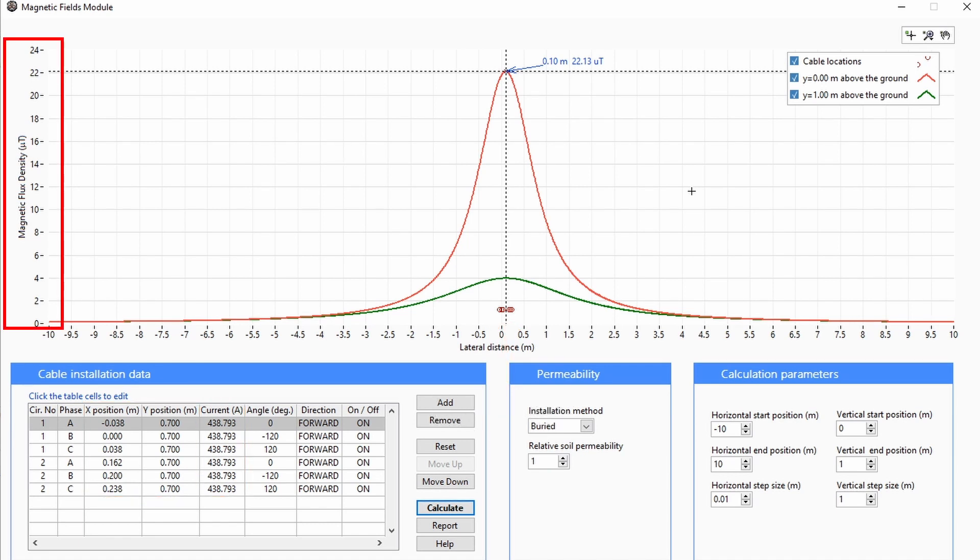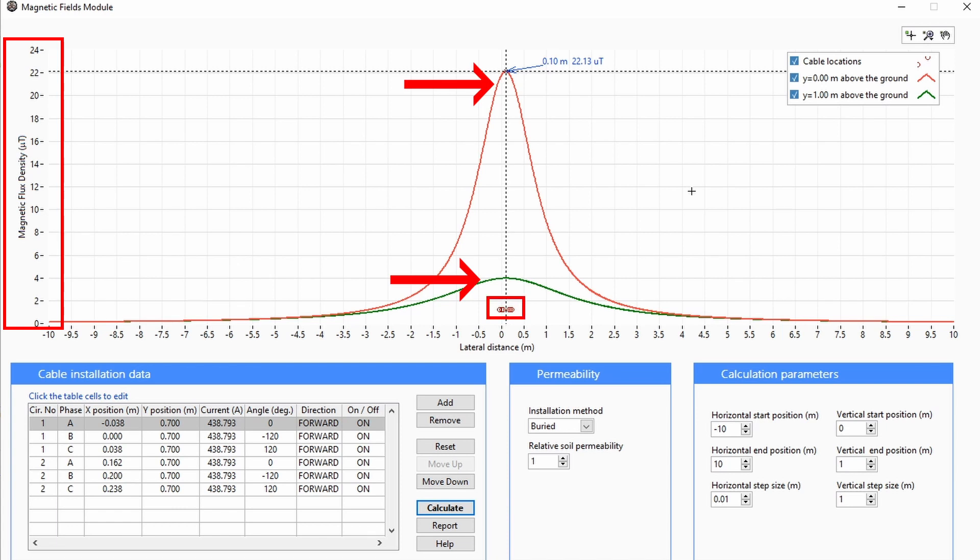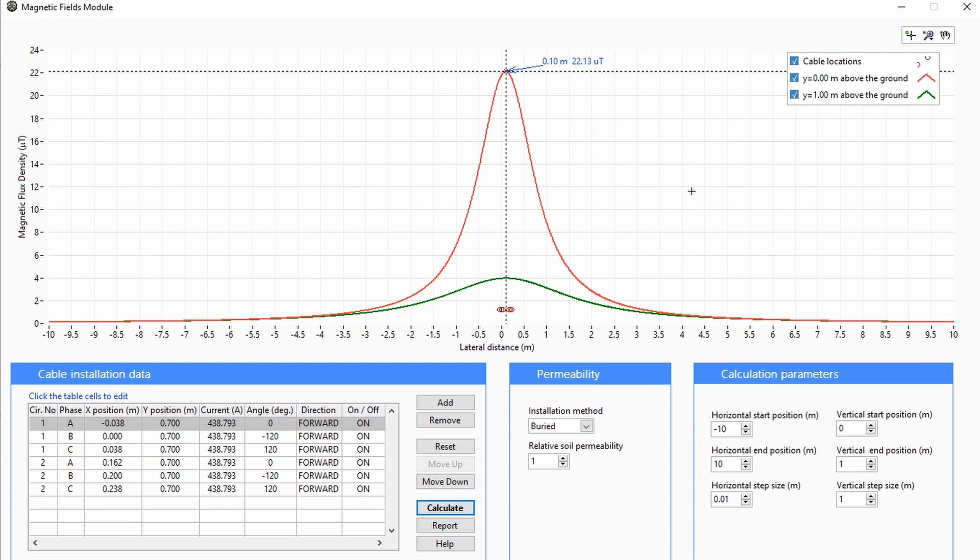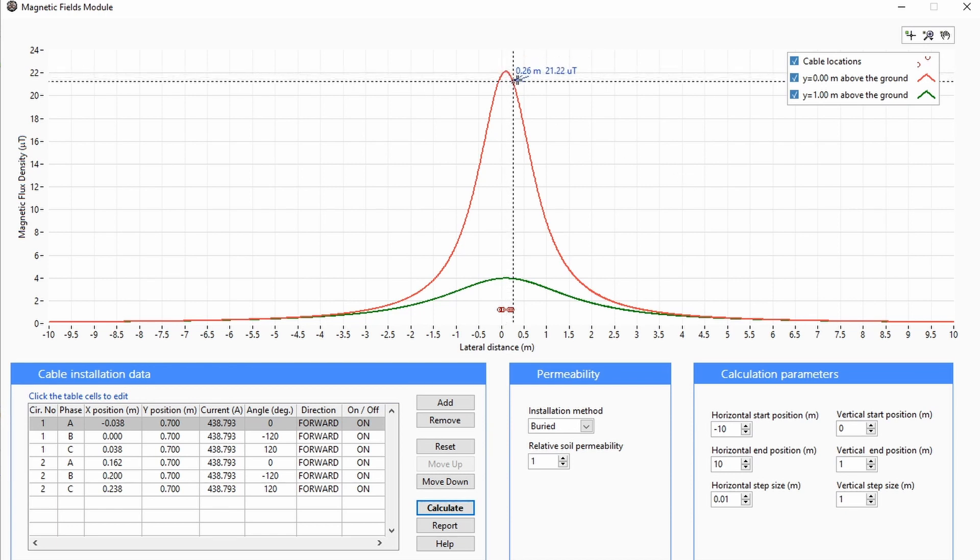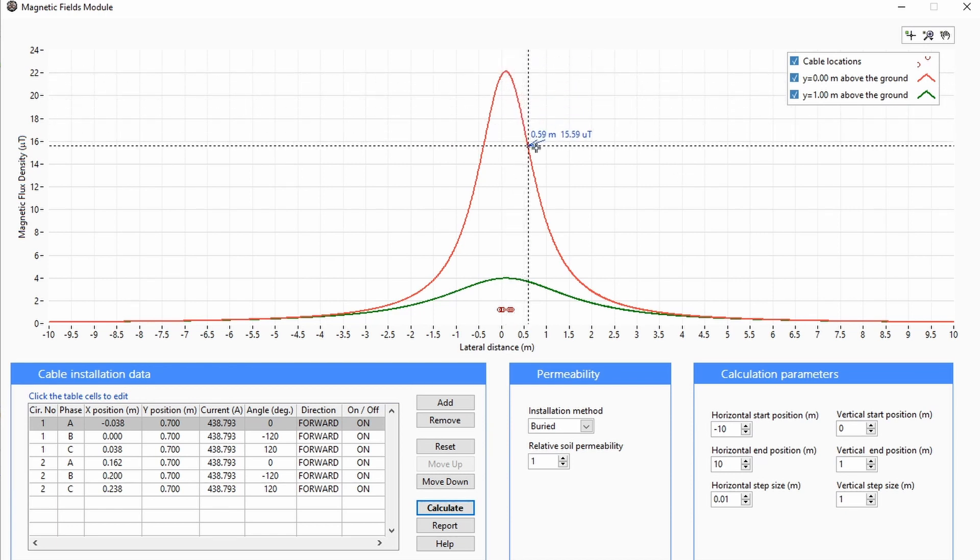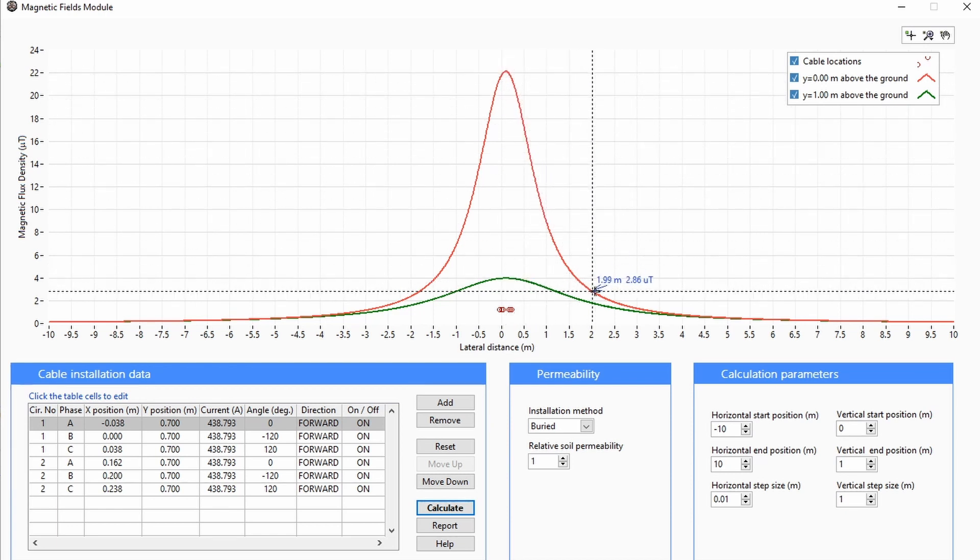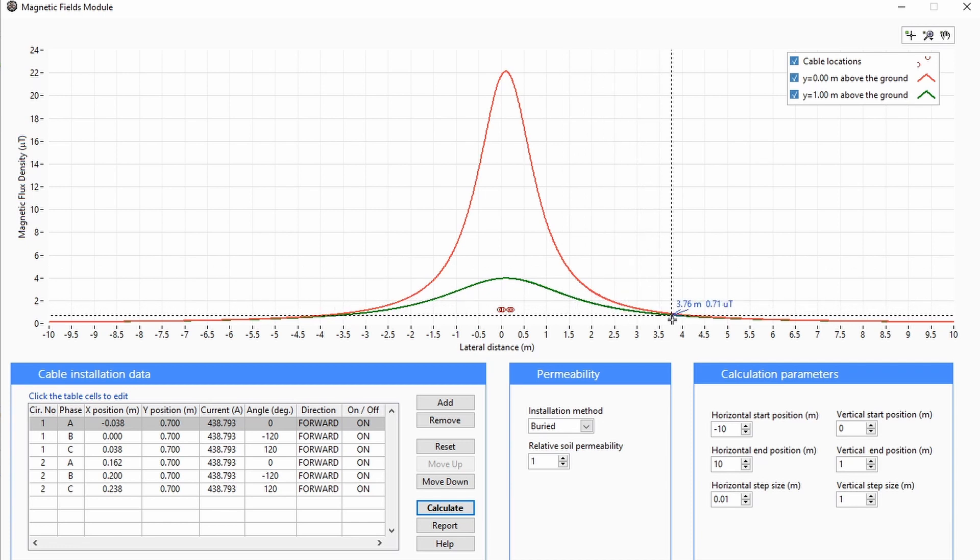Magnetic field density is automatically calculated at ground level and one meter above the ground, which is shown in the interactive plot along with the cable positions. You can drag the cursor along the curves and between the curves to see magnetic field density at any position along the profiles.